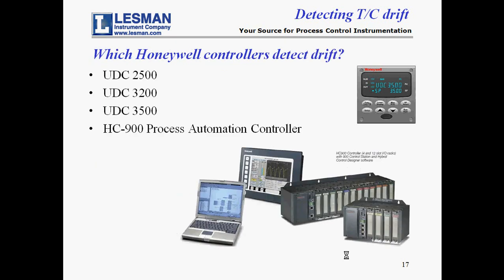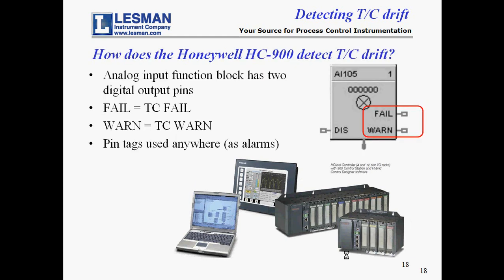Which Honeywell controllers detect thermocouple drift? The quarter-DIN stand-alone PID controllers — the UDC 2500, 3200, and 3500 — can detect thermocouple drift, as well as Honeywell's process automation controller, the HC900, which has modular IO. The HC900 provides two digital output pins on every analog input function block for the TC WARN and TC FAIL functions. The pins can be tagged and used in configuration logic throughout the HC900 and control station HMI panel, typically as alarms.